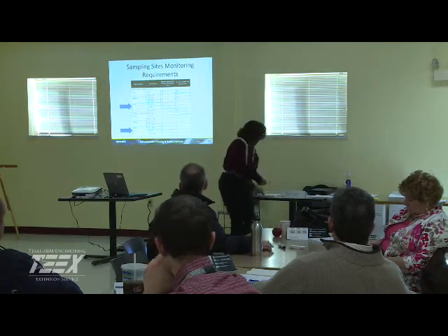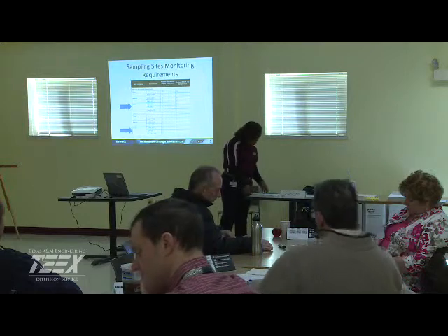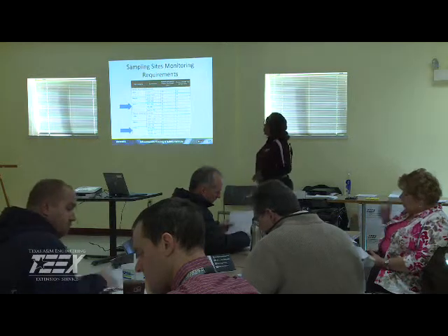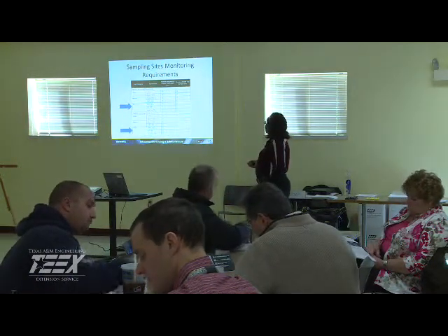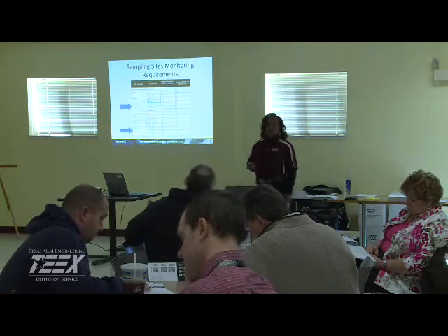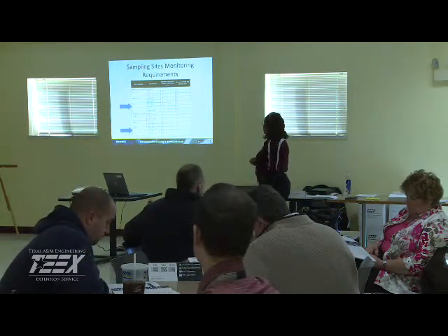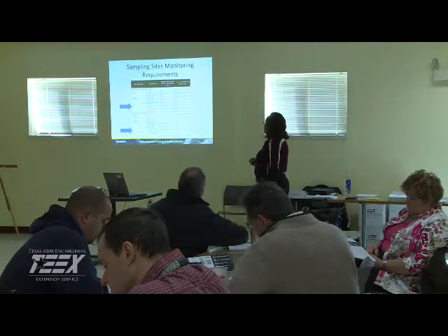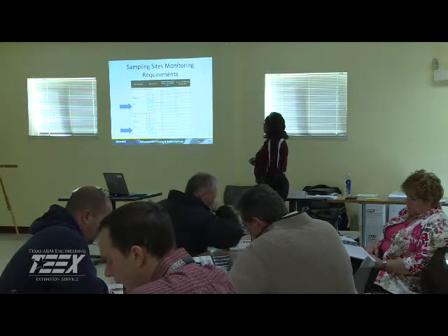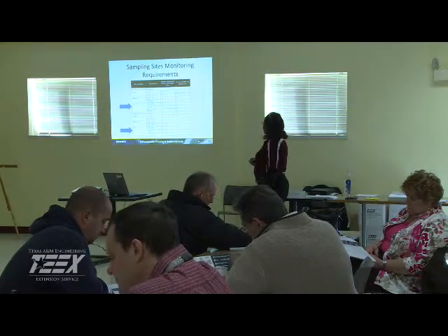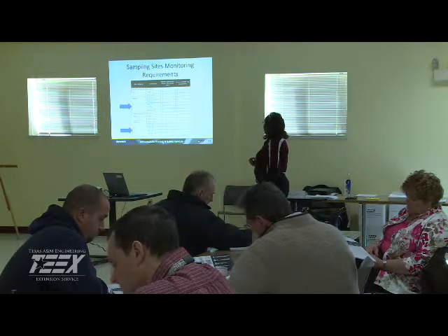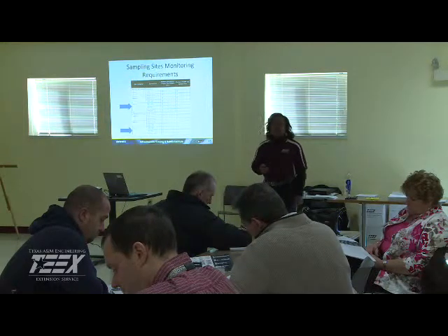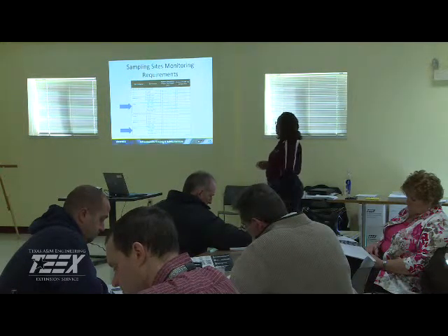If you look on page 4-6, you have a chart there. It'll give you some information as far as the size and the number of sites that you need. And since this is a small water system grant, that's the one that we're dealing with, for small systems, let's do the less than 101 population, we need 5 sites. Okay? And for water quality parameter tap sample sites, it needs 1. So 5 for lead and copper, 1 for your water quality parameters.